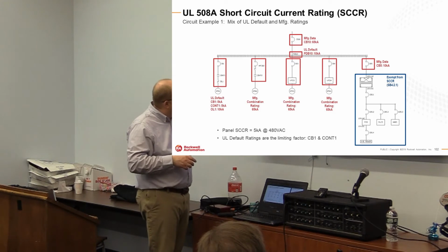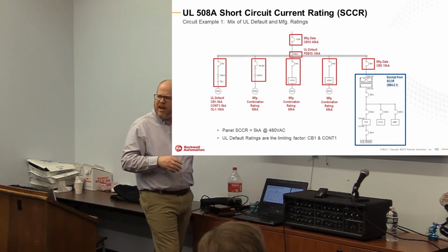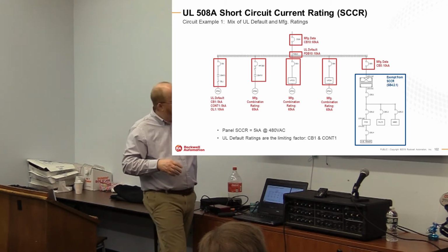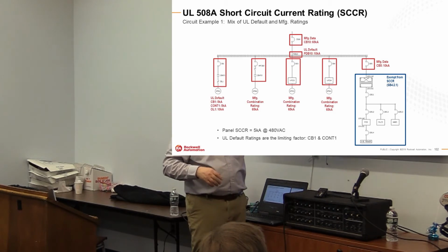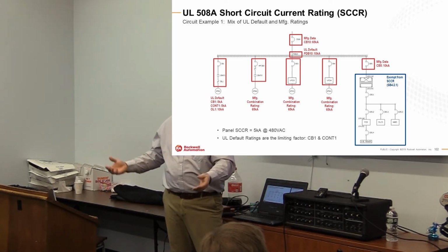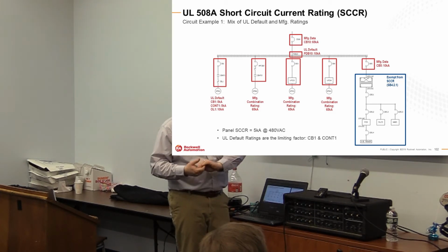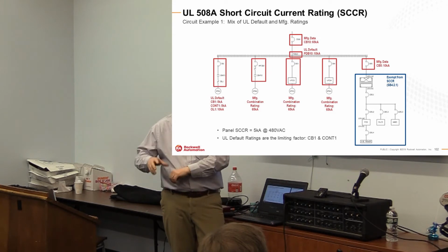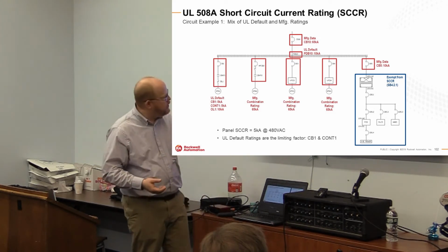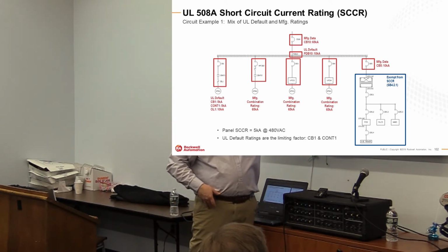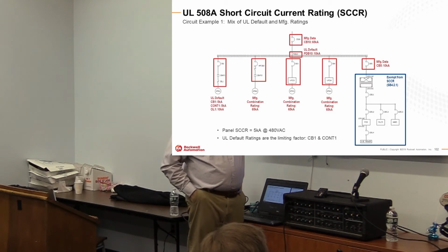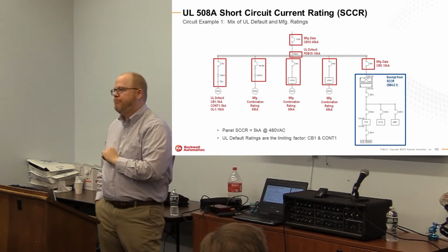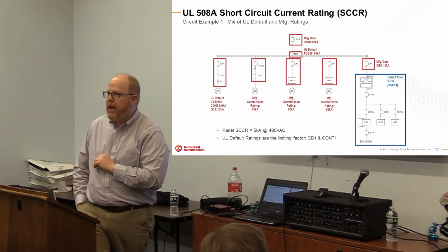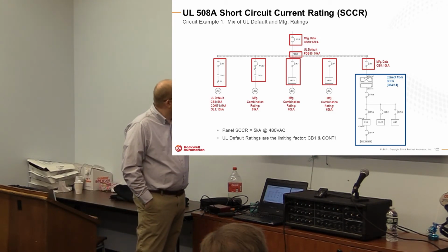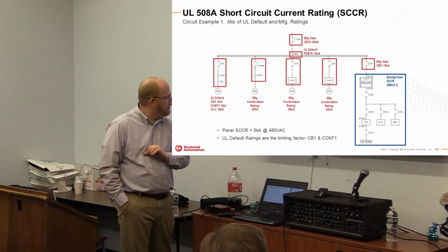We have the default ratings for this first branch. It's a mix and match of 5 and 10. So basically this branch will carry 5. Combo rating, combo rating, combo rating of 65. So each of these other branches carry 65. And the breaker upstream of the transformer is, let's say, one of those mini breakers, and it carries a 10. So we're at this point: 5, 65, 65, 65, 10. The manufacturer data on this breaker is 65 kA, but the power distribution block is a 10 kA. Okay, so what is the limiting factor? Overall panel is 5 because CB1 and overload and contactor 1 are the limiting factors to 5.